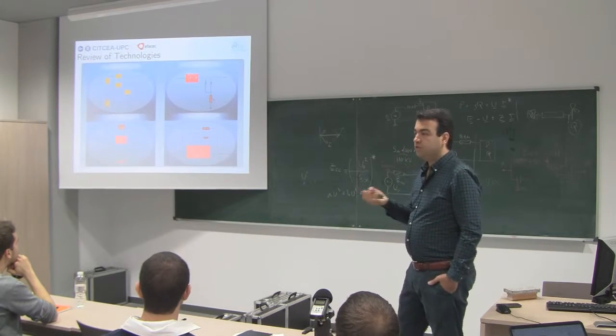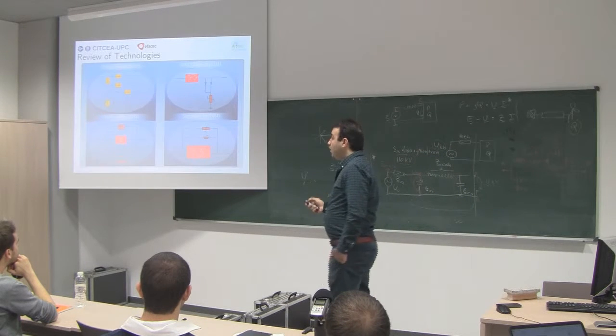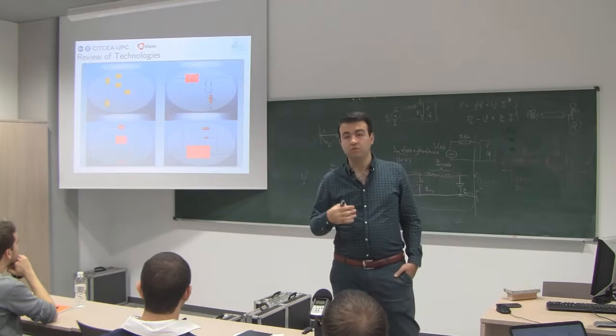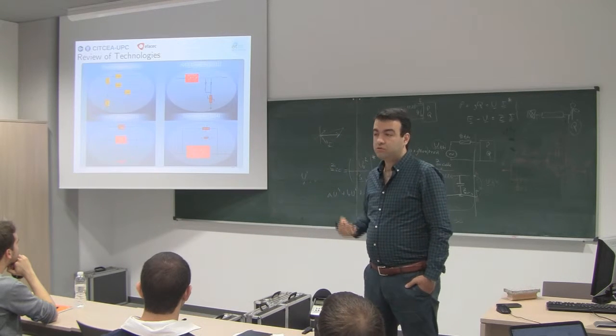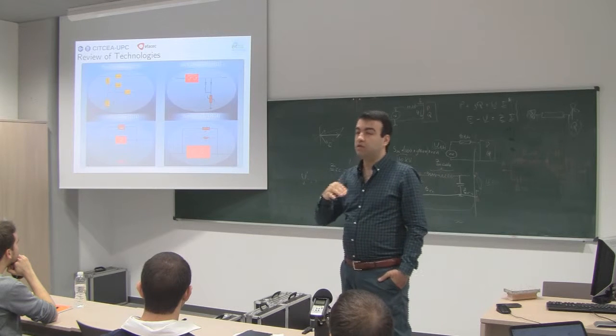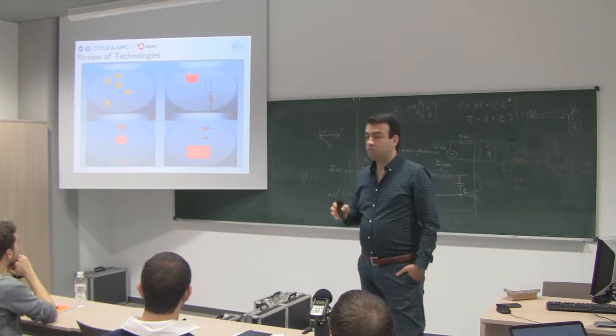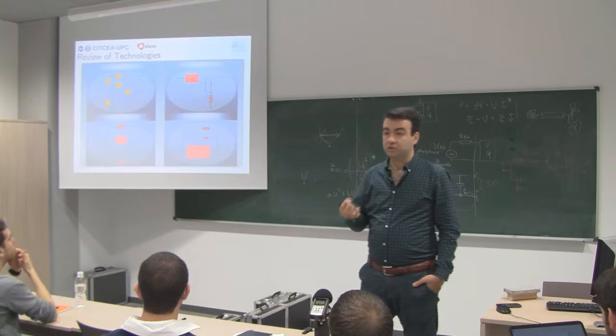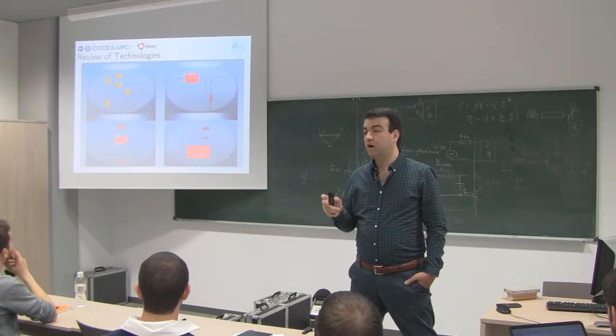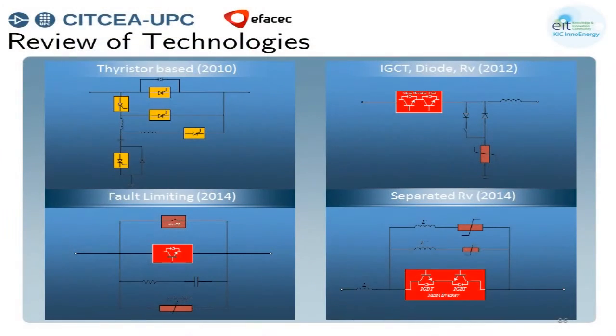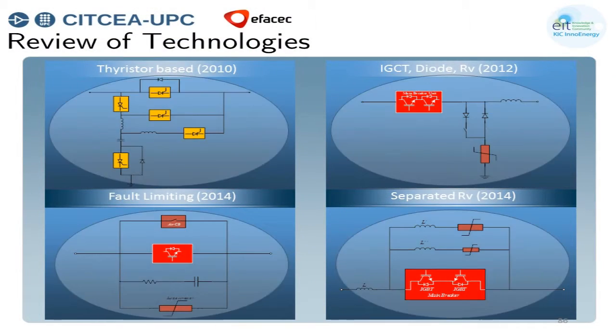So the other technologies on which research is going on are the solid state technologies, which use IGBTs or thyristors or this kind of switches instead of mechanical ones. But mainly the problem with this kind of switch topologies is the power losses, because you have relatively higher power losses inside the semiconductor devices. And it's not comparable with the mechanical ones. But since semiconductor technologies are also improving at the same time, it can be seen that in future maybe this kind of topologies will arise and will be employed to protect this kind of grids.